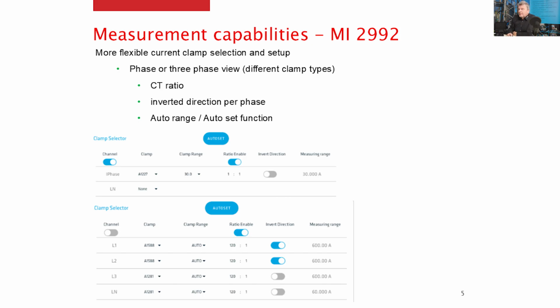separately for the inputs. We are also supporting auto range. This is available for current clamps which have more than one range. For example, our flex clamps normally have 3 ranges, for example 30, 300, or 3000. During the operation, during the recording, the instrument automatically adopts the most appropriate range of the clamps. There is also a specific functionality called auto set. In this case, the instrument will find the optimal range at this moment for the selected clamps.